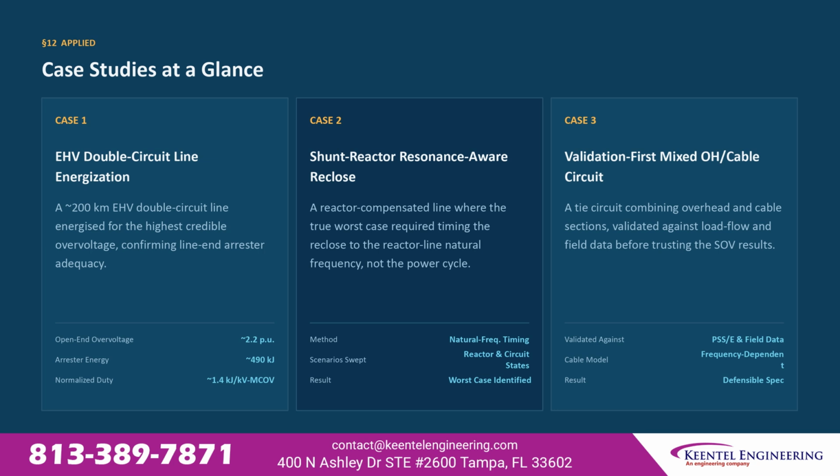Arrestor adequacy was confirmed. The second involved a reactor-compensated line where the true worst case required timing the reclose to the reactor line natural frequency, not the power cycle.